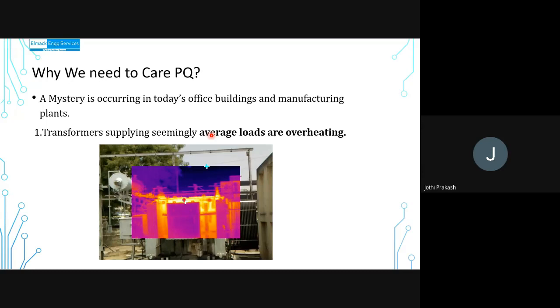But what happened earlier is that transformers were actually supplying a very average load, in the range of 50 to 60% of their loading capacity, but they were overheating. Here you can see a thermal image taken at one of the substations, and you can see the temperature of the transformer is rising, but I'm not showing any temperature degrees here. This is just for demonstration purposes.